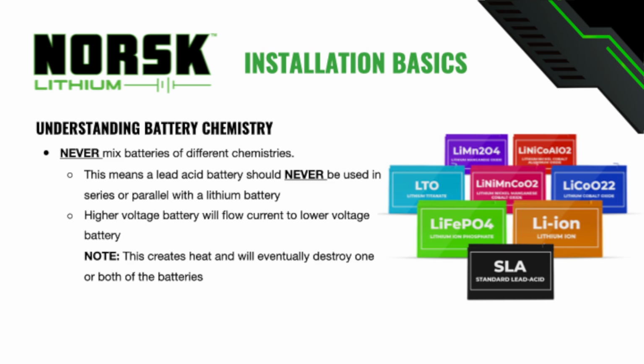If you've got a lead acid starting battery and a lithium house battery and you connect them together, the lithium battery is going to try to charge the lead acid battery essentially in perpetuity, because it's living at a higher voltage. The flow with two connected batteries is they try to get even, but that can never actually be accomplished, and you're going to create so much heat that one or both of those batteries will burn up.